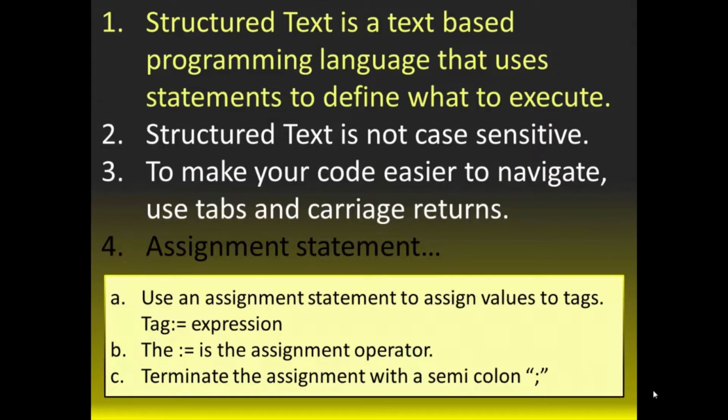In text-based languages, quite often the very first thing you do is declare your variables. In structured text, it uses values from the tag database and influences values in the tag database, but it's the same tag database that all four languages use. And the variables are declared in the tag database. Now you can actually create a tag while you're writing the language and then declare or define it. However, you don't begin your structured text with half a dozen or a dozen lines of declaring your variables.